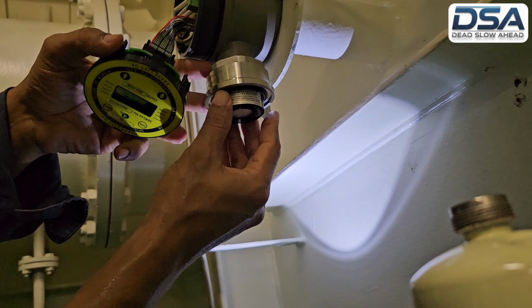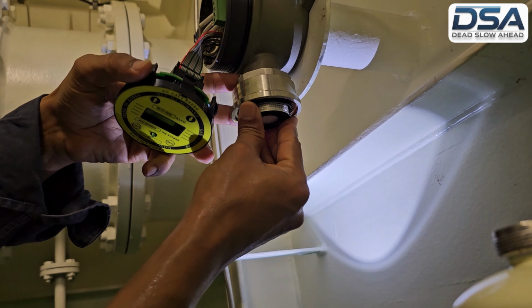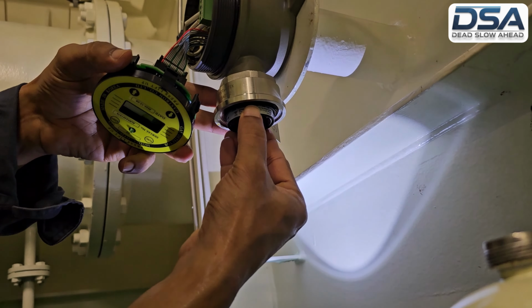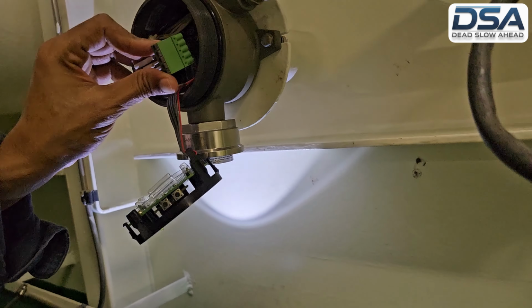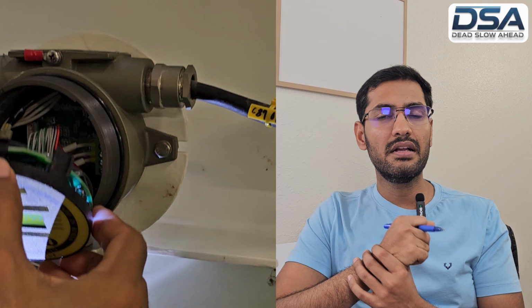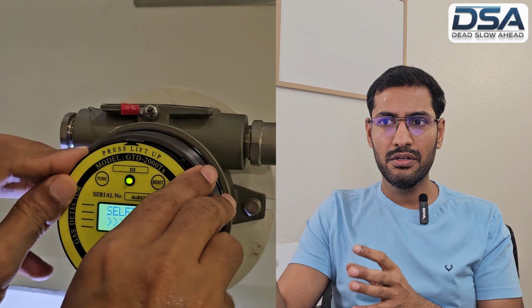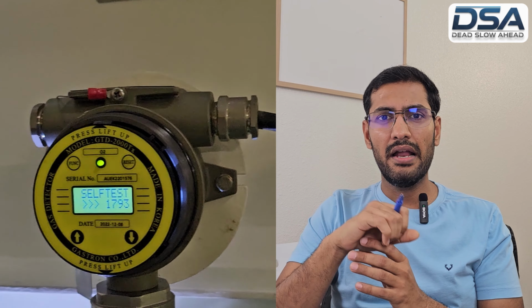Now for installation you need to align the pin with the slot in the housing, and it's a kind of press-fit arrangement. You just need to give a gentle push, and once the sensor is properly seated, it will lock in position on its own. After installation, we restore the electrical supply, and once you connect the electrical cable, the sensor goes into a self-diagnostic check. It's a self-test mode, and this takes around 30 minutes to complete.